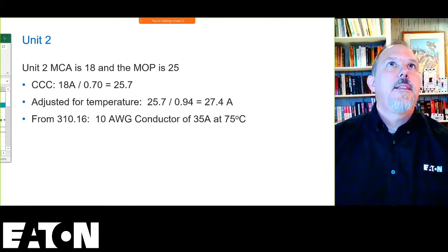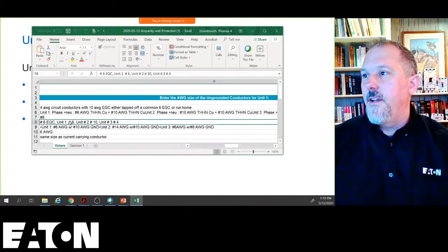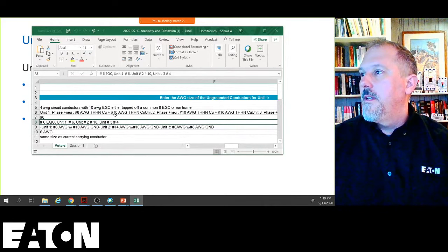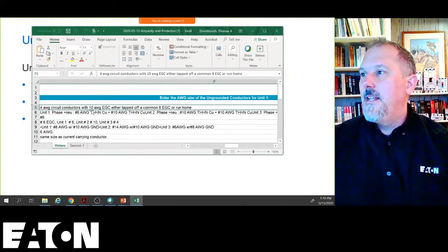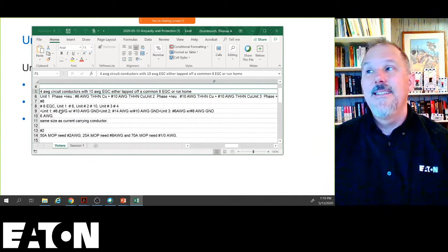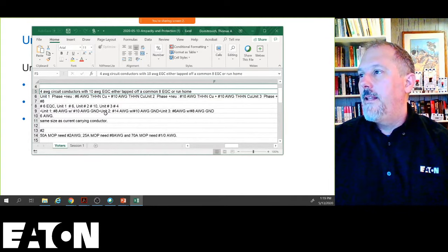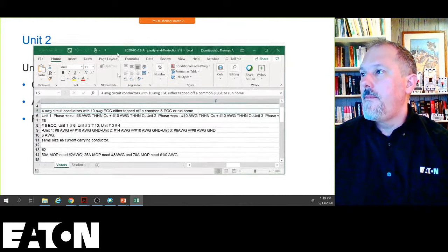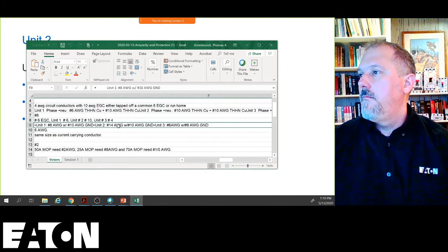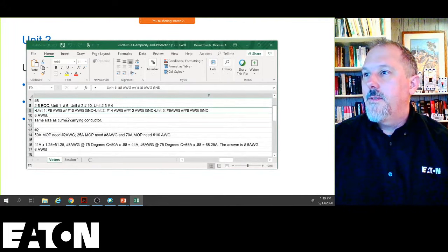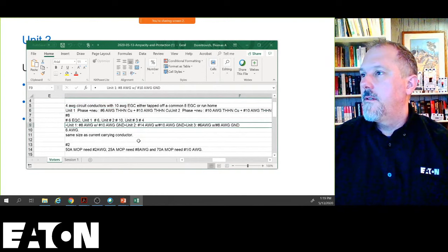So I'm looking at my spreadsheet from my submitters. I have unit 1, number 6. Unit 2, number 10. All right. So unit 1, number 6 copper, and number 10. That looks good. This gentleman here had unit 1, a number 6, and unit 2, a 14. And I'm doing a 10, so I'm not sure about this one, and I don't think that one's right. Same size as the current carrying conductor for the grounding conductors.